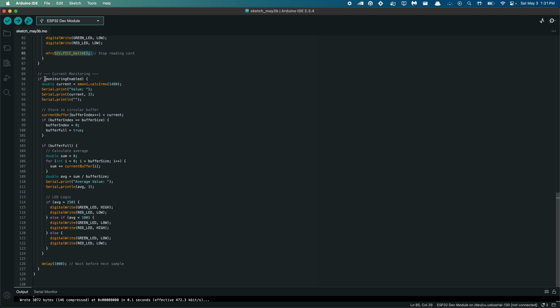In the actual current monitoring section, we check to see if the monitoring flag is enabled, and then use the energy monitor library to calculate an RMS current based off the values we get. The current transformer reads an AC source, but the microcontroller can't read a negative voltage, so we instead calculate an RMS current. This tells the library to take 1,480 samples and calculate an RMS current based off of that. It's important to note that the current we get isn't the actual current flowing, but more of a representation.